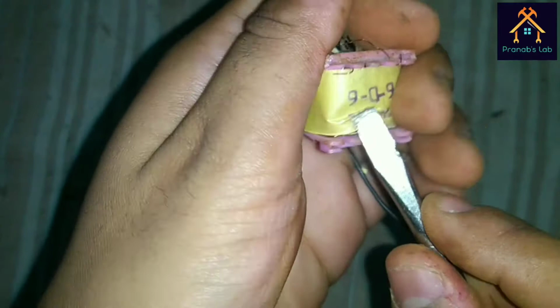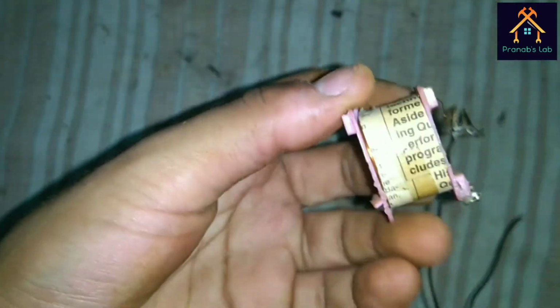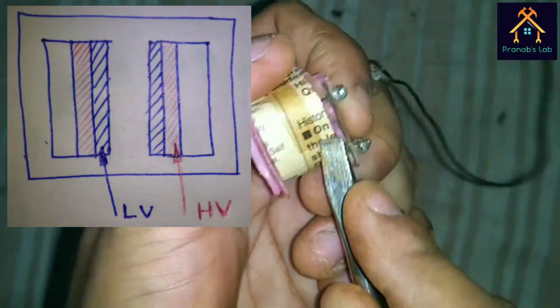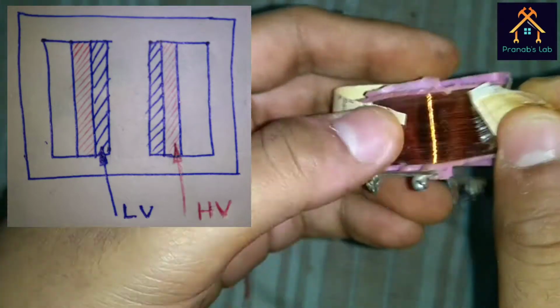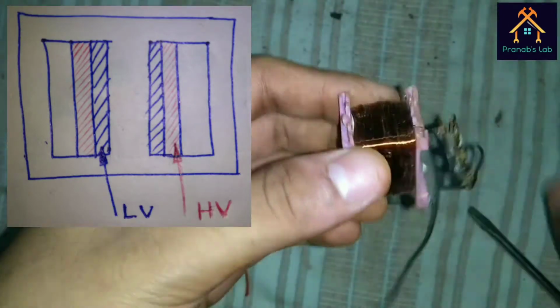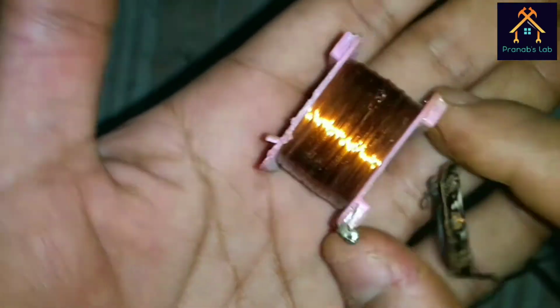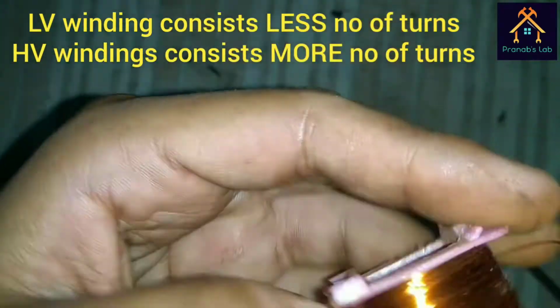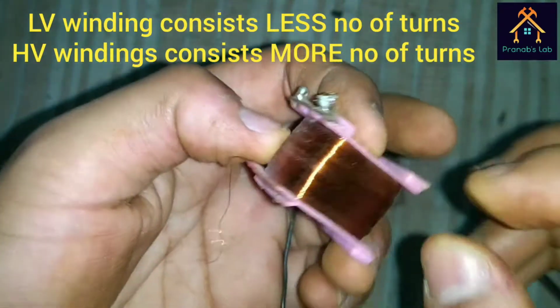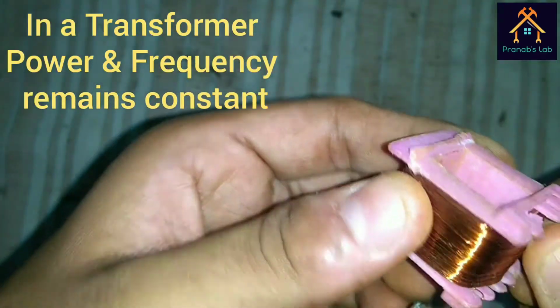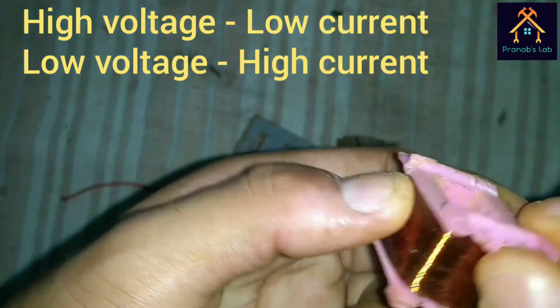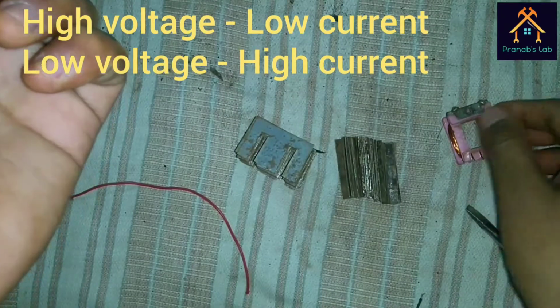Now let's remove the cover of the winding. There are two types of winding, high voltage and low voltage winding. The low voltage winding is placed near the core and the high voltage winding is placed on the low voltage winding. The thickness of the low voltage winding is higher than the high voltage winding because the low voltage winding carries more current than the high voltage winding. As we know, the power and frequency remain constant in a transformer. If voltage increases, then the current should decrease and vice versa.